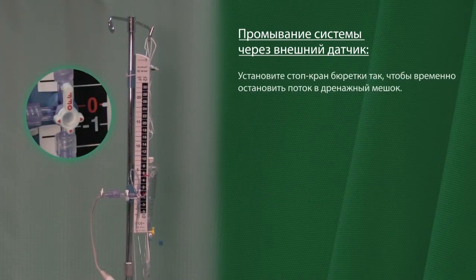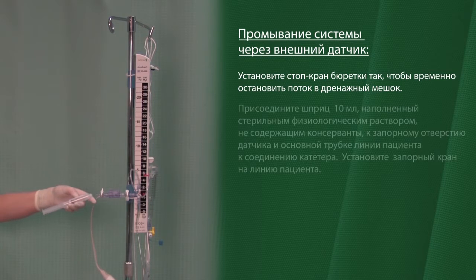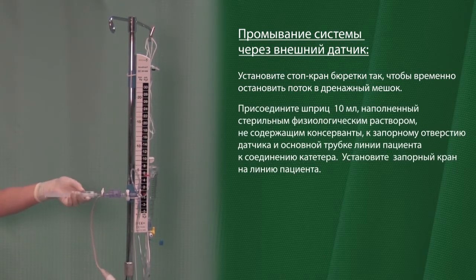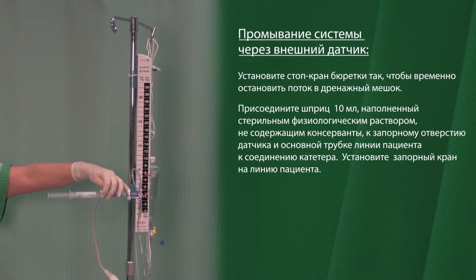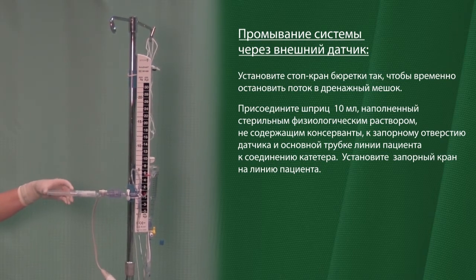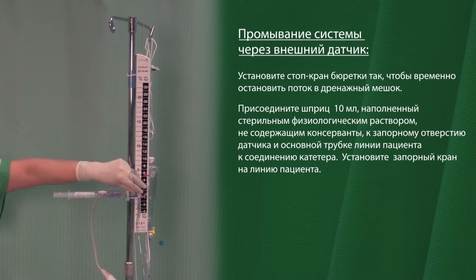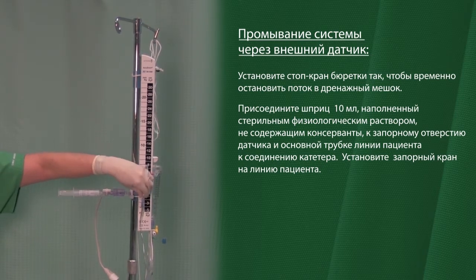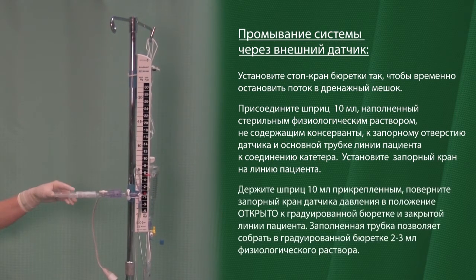Orient the burette stopcock to temporarily stop flow into the drainage bag. Attach the 10 ml syringe filled with preservative-free sterile normal saline to the transducer stopcock port and prime the tubing of the patient line to the catheter connection. Reorient the stopcock off to the patient line. Keep the 10 ml syringe attached.